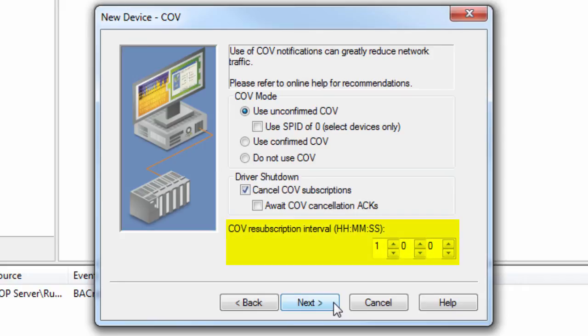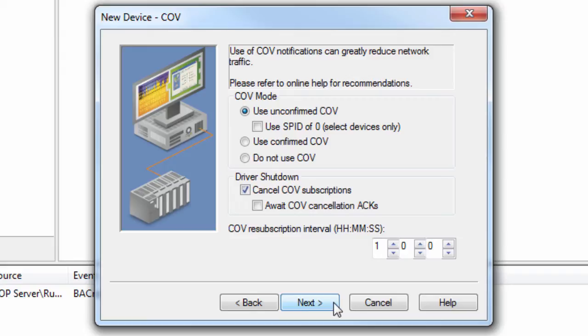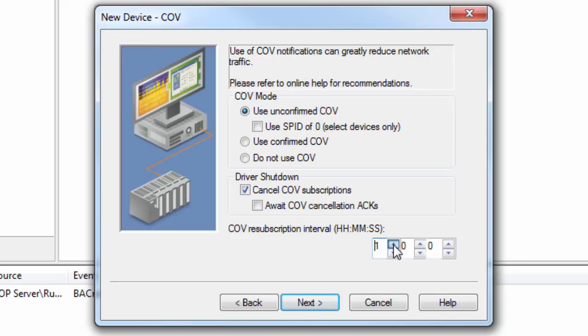An application can subscribe to COV notifications on a temporary or permanent basis. If zero is specified, the driver will request permanent subscriptions. In this case, users should check Cancel COV subscriptions to make sure the device can immediately reclaim resources that are no longer needed. Users may also subscribe to temporary subscriptions. One second prior to the end of the subscription, the driver will automatically renew the subscription for active tags. Click Next to set the tag import settings.